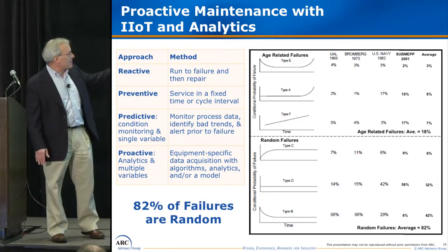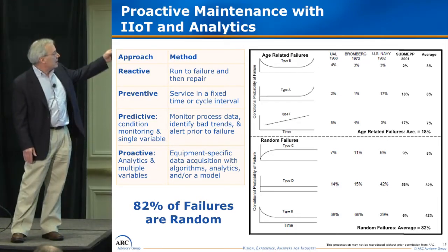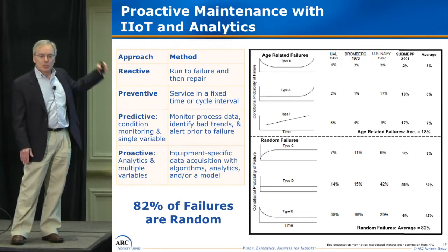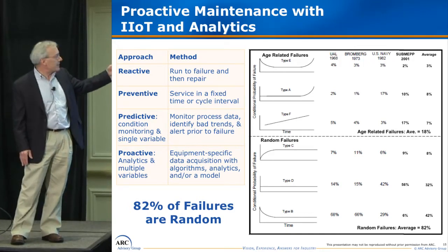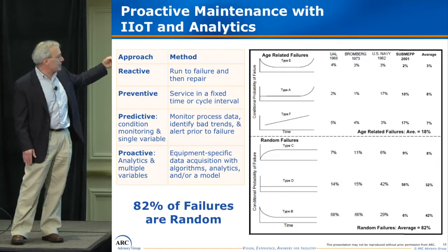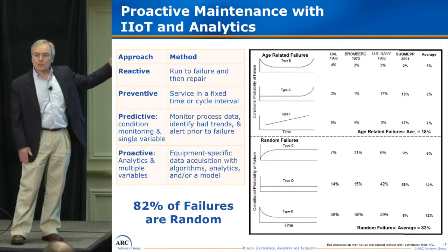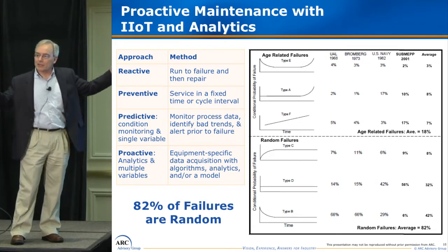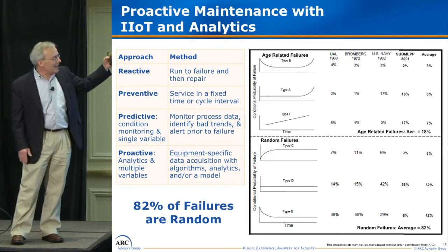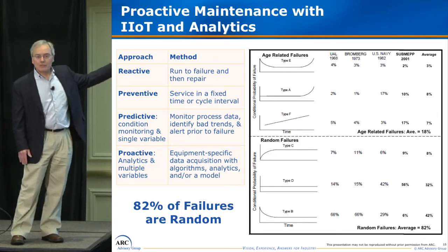So now that starts to bring me over to the left side of the slide, where it's more of a maturity model of how you maintain assets: reactive, preventative, predictive, and proactive. And the point of this slide is that your preventative maintenance only makes sense for, round numbers, 20% of your assets. Again, reminding us of what a great philosopher Pareto was. And the other 80% of your assets really need predictive condition monitoring type solutions.